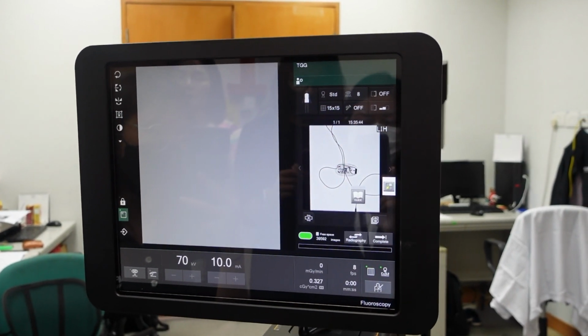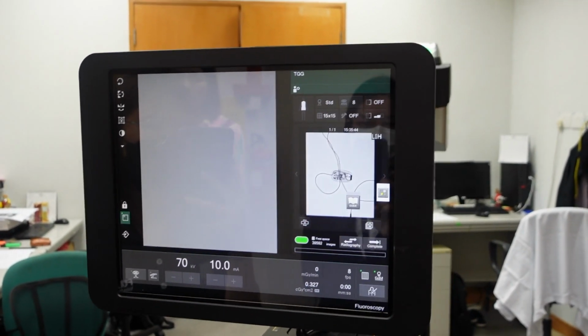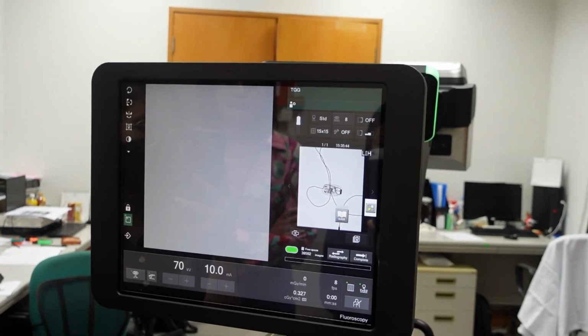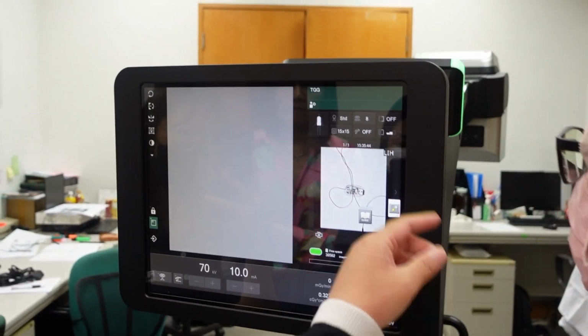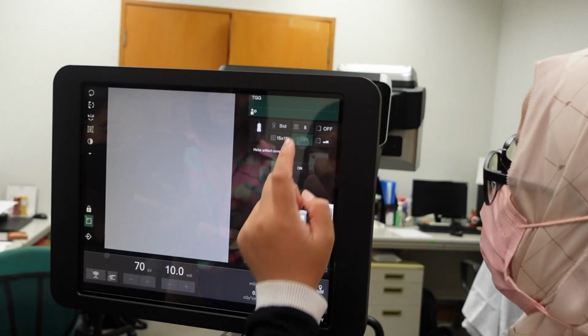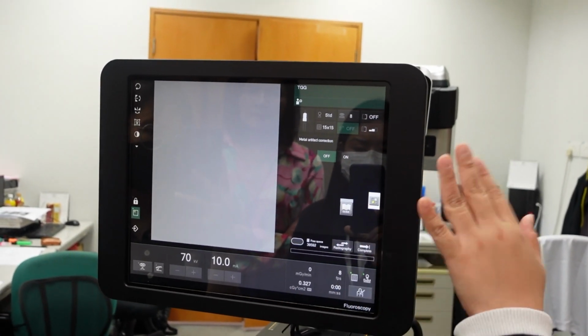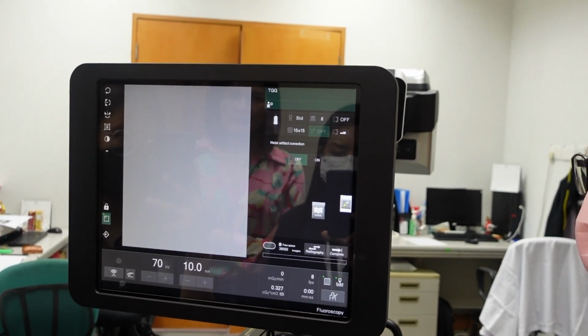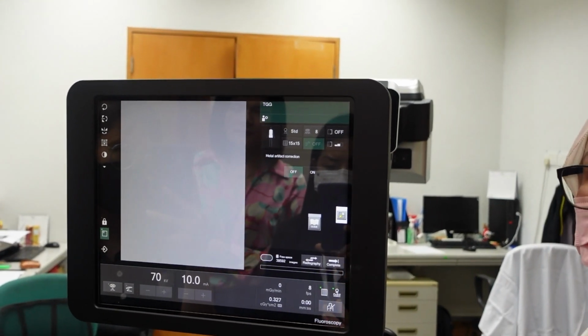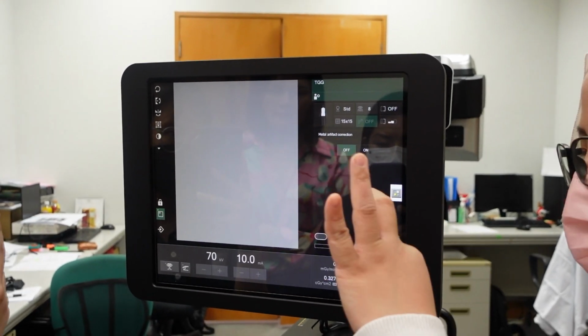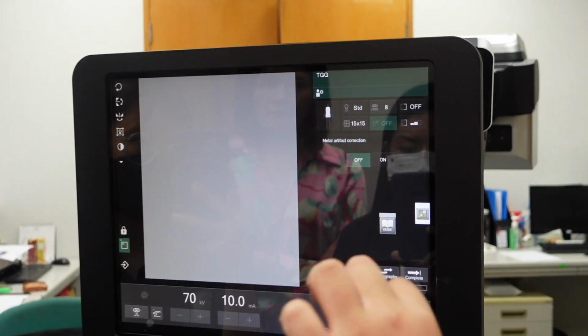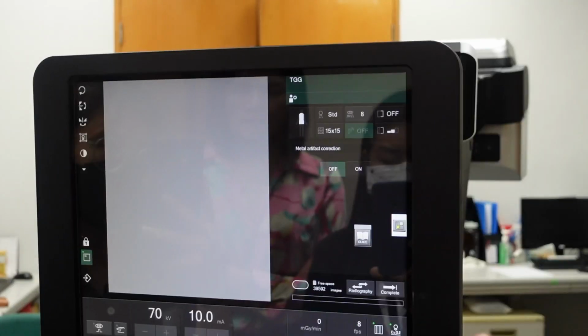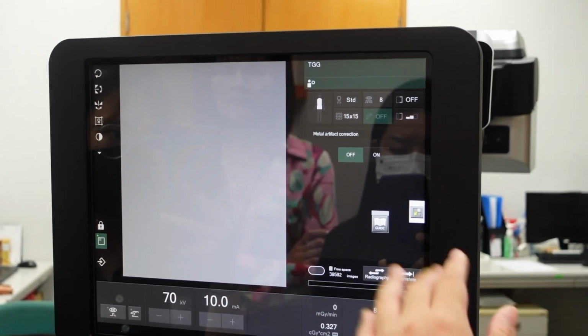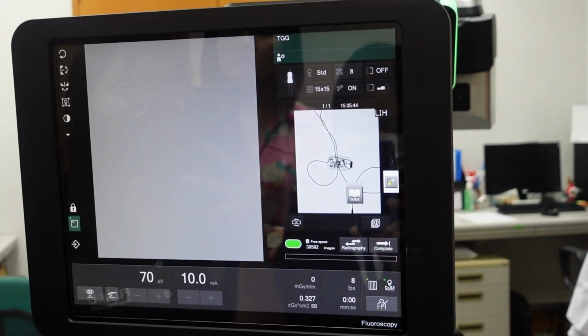Now you can only see the effect after you select this and then you acquire again, you screen again, then you can see the magnification effect. This is the so-called metal artifact correction. I was hoping it was supposed to suppress the metal, but actually it's just to avoid this halo-looking artifact effect. It's suppressed a little bit when you turn it on, but it doesn't remove the metal entirely.